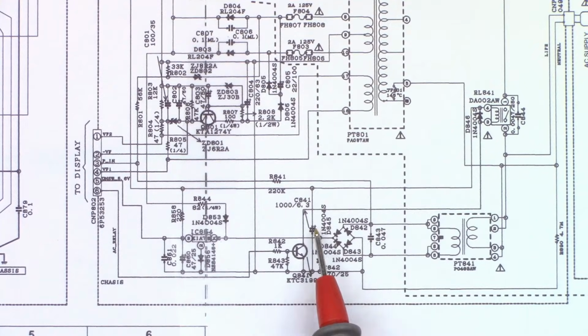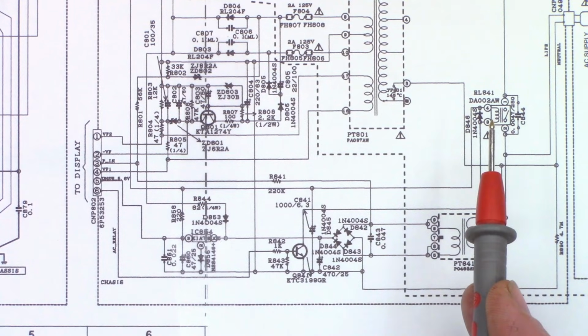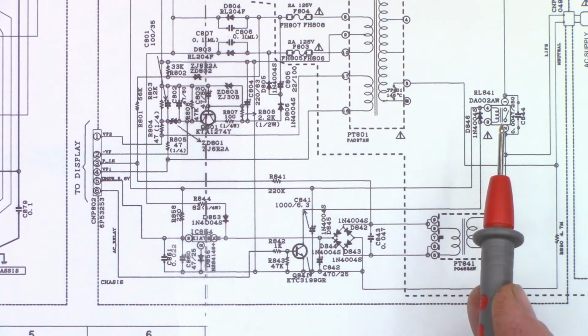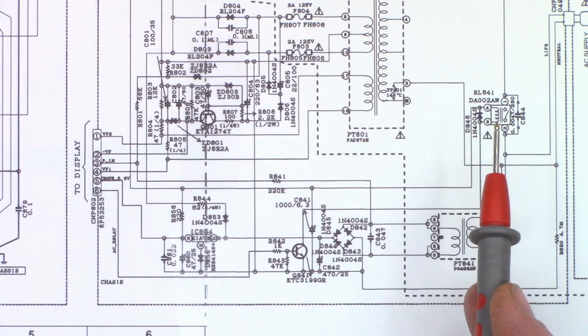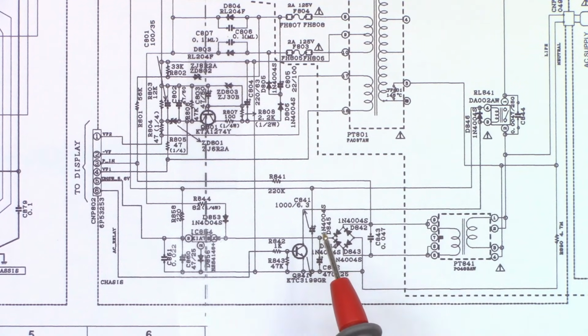The other issue that could be happening is this 1000 microfarad capacitor, which is like a stiffening capacitor. It's only meant to help pull in the contacts on the relay. Once it's pulled in, it doesn't need that much voltage to continue to hold the contacts. So I want to check the ESR on that capacitor. On a 1000 microfarad cap, I'd like to see maybe a quarter ohm or less. Let's check that ESR and see what it looks like.